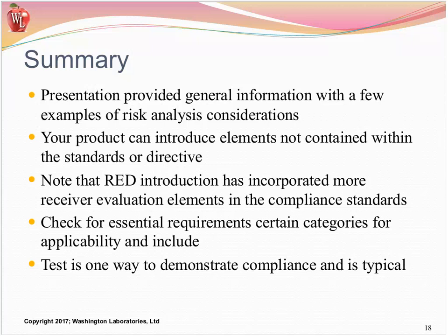It may not be just one test. It may be that when I put this thing into the extreme temperature range, how many tests have to be done for that applicable standard. So we've got to pay attention to that, and your risk analysis needs to consider that I've covered all of the tests in the laboratory. That in the laboratory has been communicated, and you reviewed that it is in fact covered. So putting this risk analysis in enough detail in front of the laboratory sometimes makes sure they evaluate more thoroughly than you might expect, and document more thoroughly if you place that requirement for them to provide you that documentation.